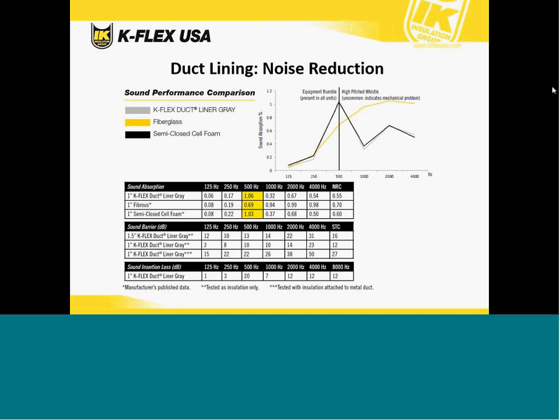The good thing about a closed cell elastomeric duct liner is that it does perform acoustically very well at the lower to mid-range frequencies, which is where a lot of the equipment noise and rumble is located. Your higher pitch frequencies above 1,000 to 2,000 hertz are generally from an airflow issue, which means the system needs to be rebalanced. The reduction really centers around those lower to mid-range frequencies, which can reduce your compressor and fan rumble noises, which are very distracting to occupants in the space.